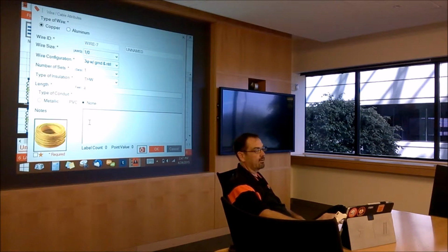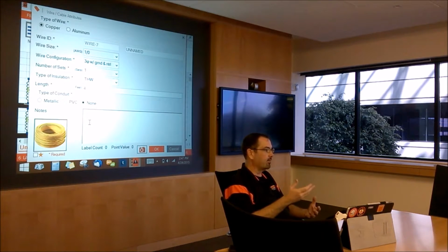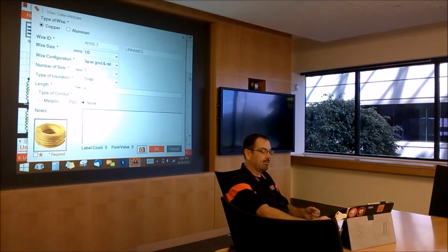Now there's a notes area, and the notes area again is for the electrician, if he's observant enough to make an observation rather than just collect data. They'll put in there's a possible code violation, meaning that the wire doesn't match up with the fuse, or there's an insulation issue, or there's a conduit issue, whatever, there's too many wires in this conduit. So they're going to point this out. Hopefully, you get a good electrician who's going to be conscious and looking at these things from a code point of view, making those notes for you, taking those pictures. If there was an issue with it, they could take a picture of it and you could reference that, giving you more information than just raw numbers in the field to insert into your SKM drawings so you can make better recommendations in your cover letters and consult with your end customers better.